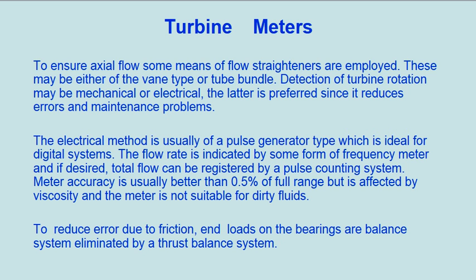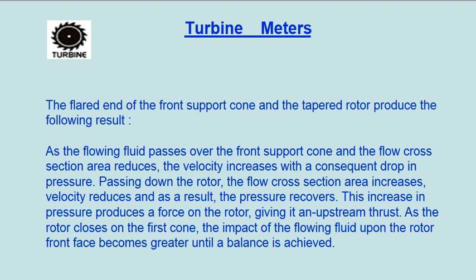To reduce error due to friction, end loads on the bearings are eliminated by a thrust balance system. The flared end of the front support cone and the tapered rotor produce the following result: as the flowing fluid passes over the front support cone and the flow cross section area reduces, the velocity increases with a consequent drop in pressure.